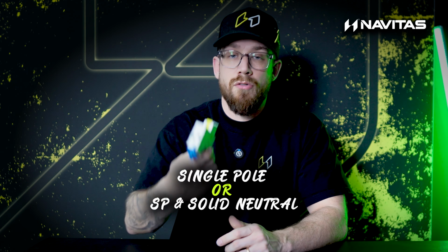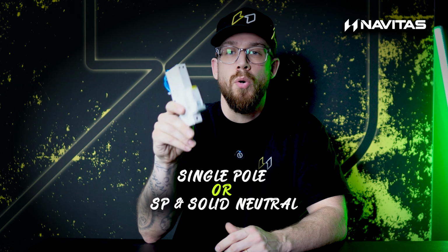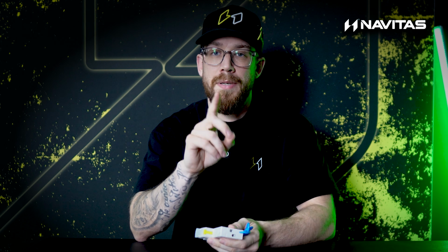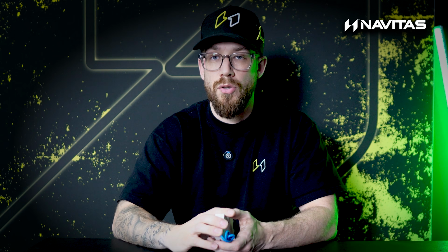Most commonly, you'll find across the market, is your single pole or single pole and solid neutral, okay? Now, it's important to understand that when you see SP and N, it could be a single pole device. And what do I mean by single pole? I don't mean that it isn't a neutral circuit. What I do mean is it will only switch the line side of the circuit, leaving the neutral side open for current to flow through. So these are your standard sort of tall RCBOs, and most of them are single pole or single pole and solid neutral. But be aware there are compact RCBOs that are also only single pole or solid neutral devices.